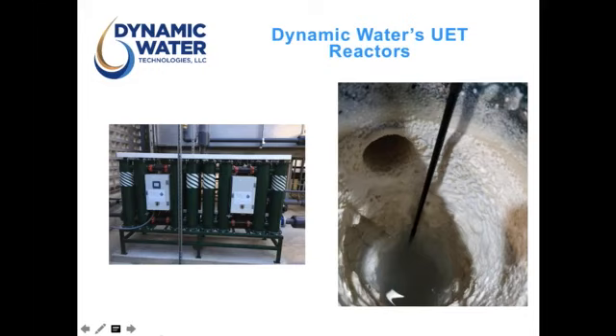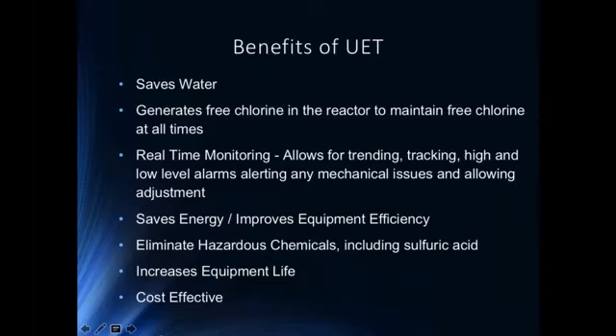And then if you look on the outside of the reactor there, you will see a white precipitate. Essentially, the way the system allows us to cycle up much higher is we are actually precipitating hardness, calcium, magnesium, silica, the different minerals in the water selectively in the reactor. So we're removing those minerals that are not stable, precipitating them in the reactor, and therefore the heat exchange surfaces stay clean. And on our regular service visits, once we come out monthly at least, but once every 3 months or so, we have to clean that material out of the reactor.